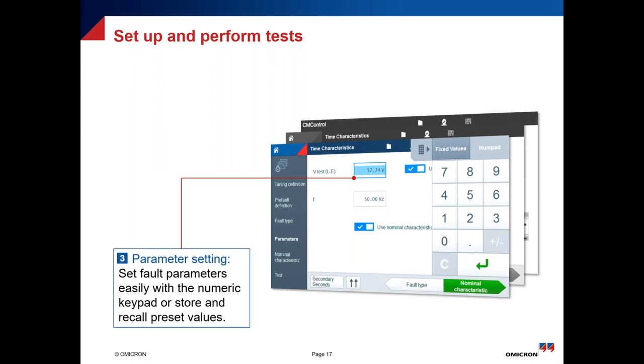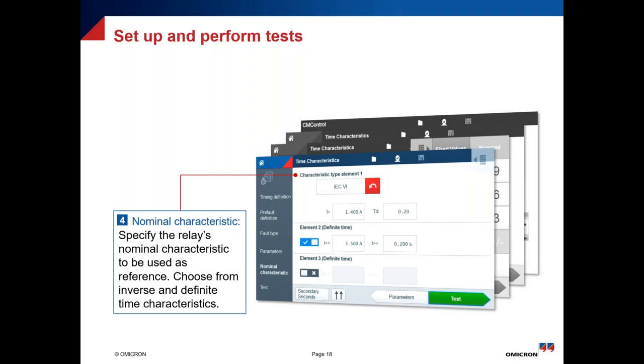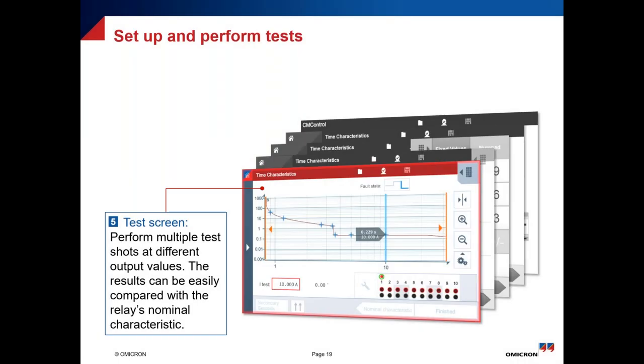Here is an example showing how to control the injection value — very easy and straightforward. As mentioned, we have a wheel for gradual increase and decrease, and a keypad to enter numbers directly. The display shows the nominal characteristic. We have up to three stages for overcurrent — for example, inverse or very inverse characteristic — with pickup value, time multiplier, and stages two and three as backup. If you enable all three stages, you get one report covering all three at the same time. You can export the result to a test report and print it later.